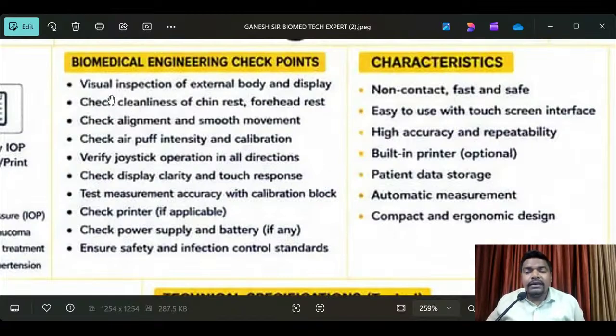Number 1 point, visual inspection of the external body and display. Number 2, check cleanliness of the chin rest and forehead rest, and check alignment and smooth movement, and check air puff intensity and calibrations, and verify joystick operation in all directions. Check display clarity and touch response. Test measurement accuracy with a calibration block. Check the printer if applicable, and check the power supply and battery if any. Ensure safety and infection control standards. See, these are the points I'm giving here.